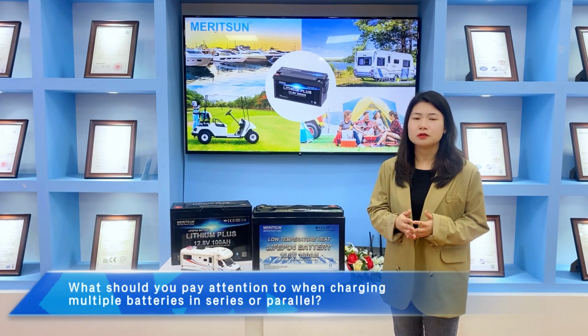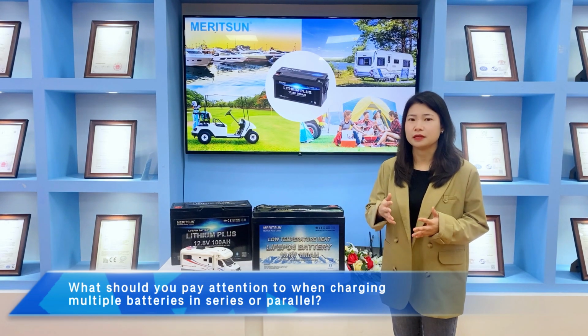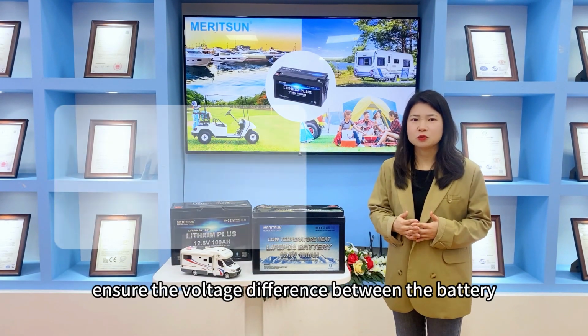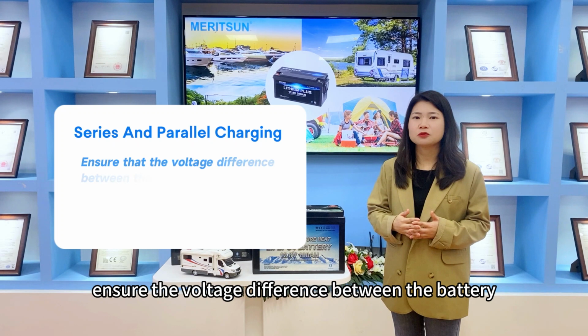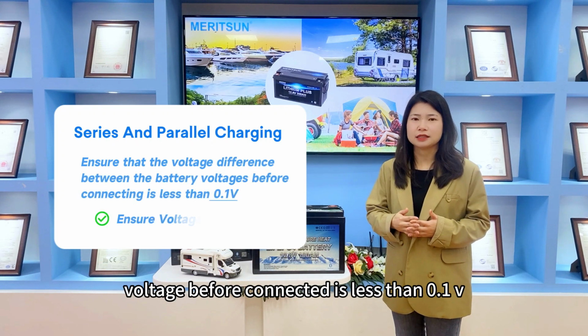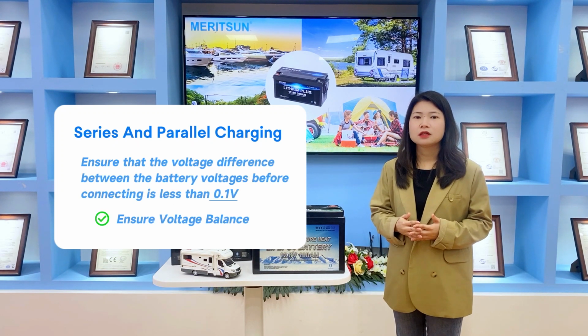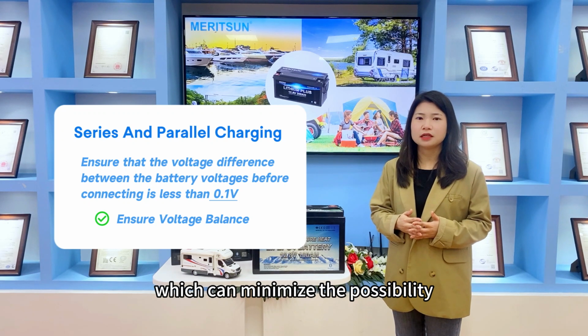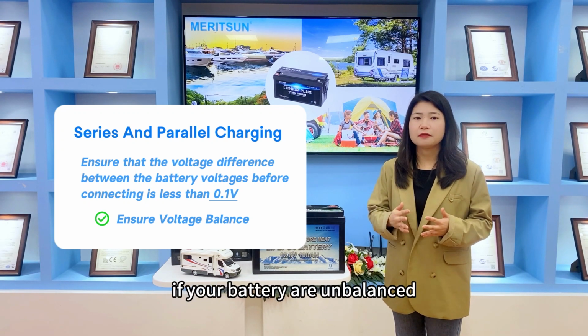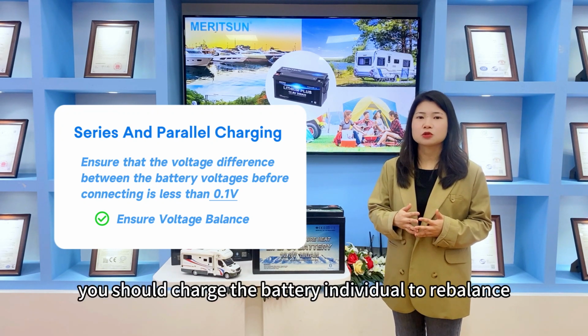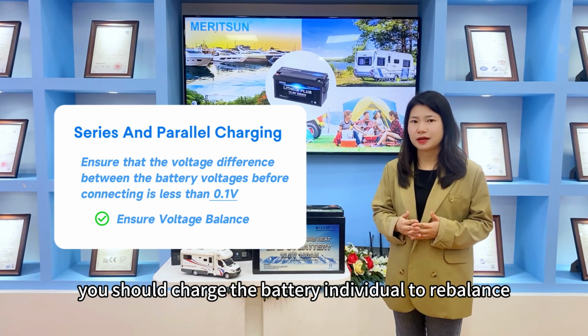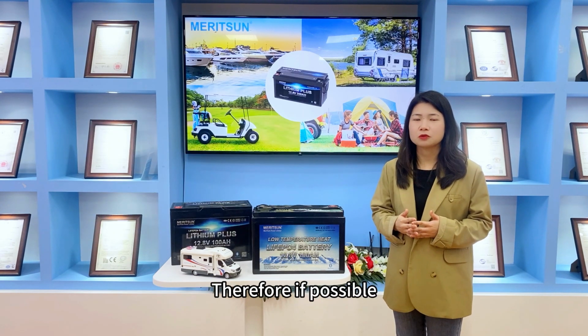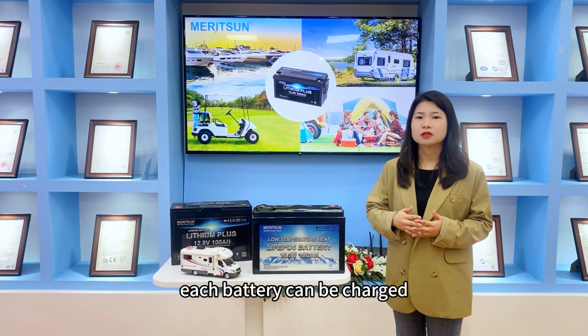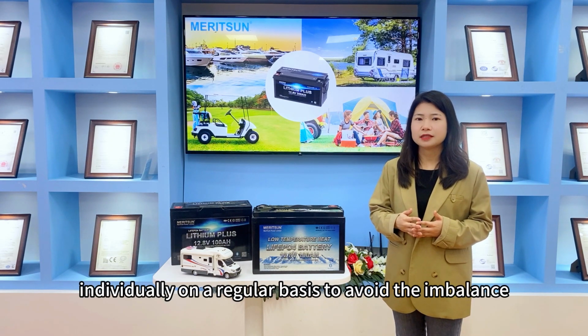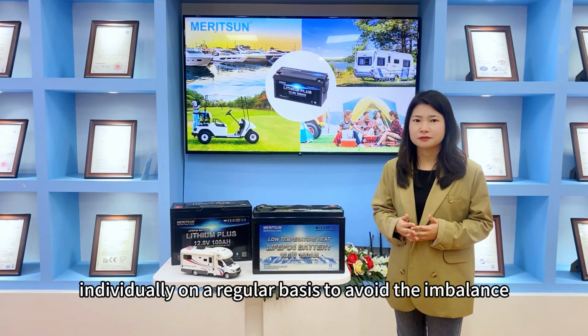Do you know what you need to pay attention to when charging multiple batteries in series or parallel? Ensure the voltage difference between batteries before connecting is less than 0.1V, which minimizes the possibility of imbalance between cells. If your batteries are unbalanced, you should charge them individually to rebalance. So if possible, charge each battery individually on a regular basis to avoid imbalance.